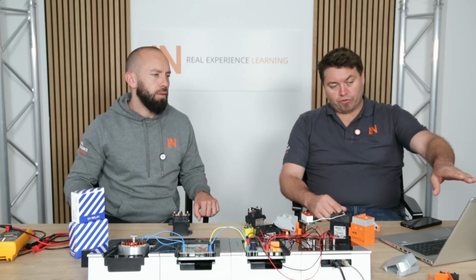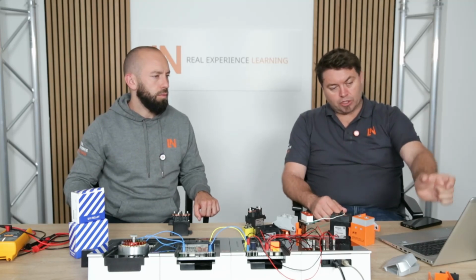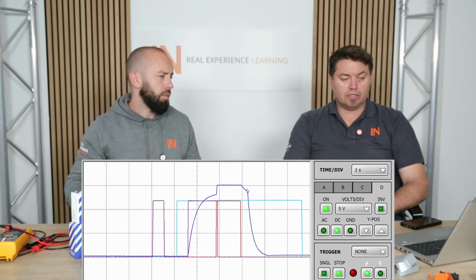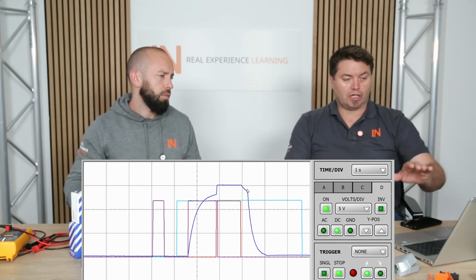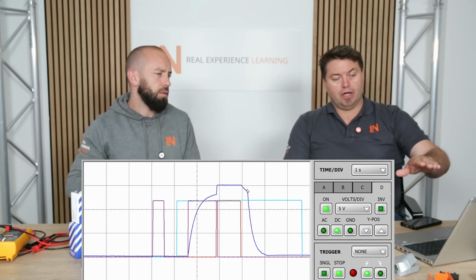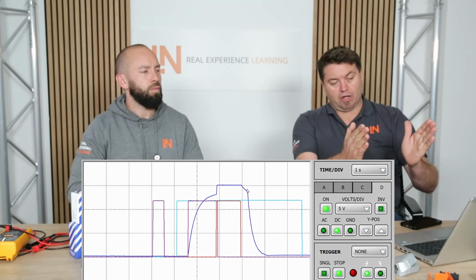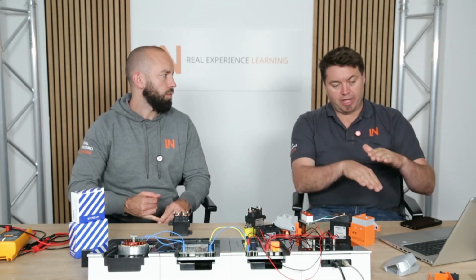Now what we've got here is the active discharge component of that signal, at 1 second per division. If we have a look at that, it's done within about half a second, down to a safe voltage, and that's the case at 400 volts as well. Like on a vehicle, half a second is roughly standard. Passive discharge can take 5 minutes when you're talking 400 volts or so.